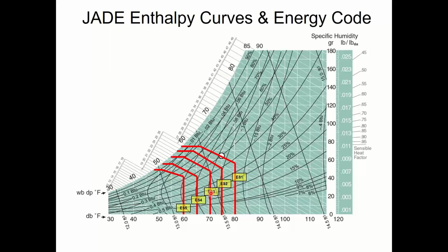They have curve 1, 2, 3, 4, 5. Their old stuff from the 90s and 2000s had A, B, C, D. Those curves are unrelated to these curves. They look completely different. We don't need to talk about them right now at all. Just know you're going to follow one of these curves. And if I want to go with a code compliant, see, I'm going to plot that yellow line back on there. That's the code compliant curve. I'm going to plot these purple ones on to show the plus or minus 2 BTUs and the plus or minus 2 degrees. So anything between the 2 purple lines is code compliant.